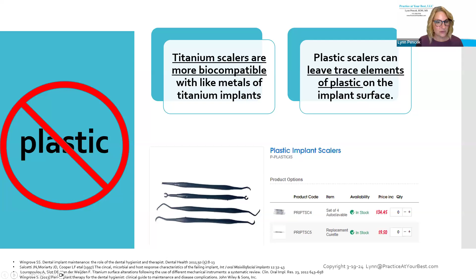So we have two things happening. One is the concern that the instrument may change the surface texture of the implant. This is why we only want to use these instruments when we absolutely have to. And the other is, if we use the instrument against the implant, is the instrument leaving little pieces of metal onto the implant? And if it is, and you're working with a stainless steel instrument, you're leaving stainless steel behind on titanium, which is not biocompatible. So the less you instrument, the better off you are. If you have to instrument, you want to work with something that's biocompatible and effective for the task. Pick the right tool for the right job is what I'm saying.